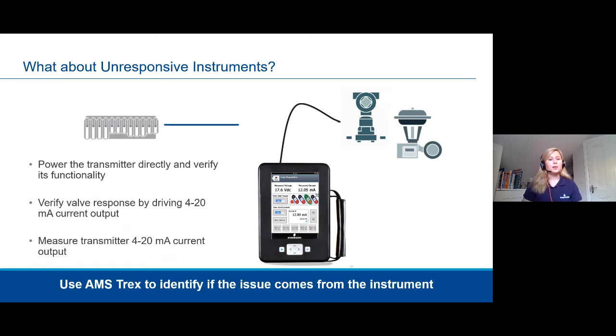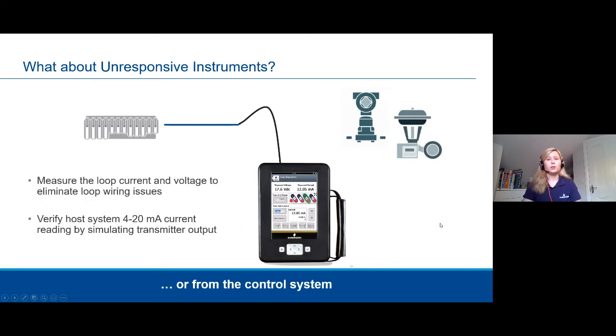A top tip that I was always given as an engineer is start with the hardware, the wiring, and then check the software configuration. So where in the loop is the issue? You can power the instrument directly from a handheld communicator such as the AMS Trex, and then help diagnose the problem, simulate the instrument, and verify the 4-20 milliamp readings to check the loop for wiring issues.